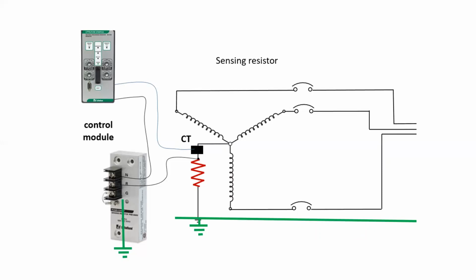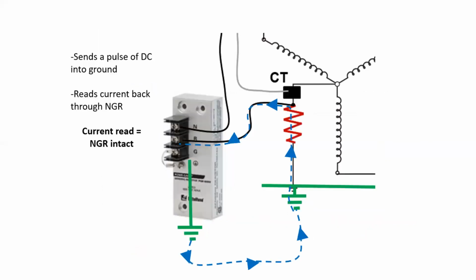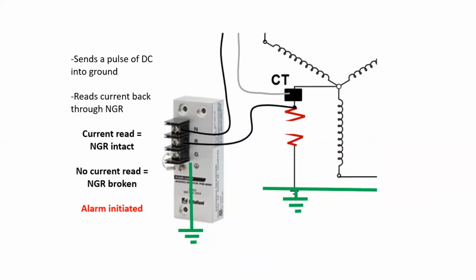And in order to accomplish that, what we typically have is something called a sensing resistor. So the sensing resistor connects with a ground terminal as well as a wire that connects to the top of the resistor. And it connects back to the control module. Its purpose is to continually verify that the resistor is intact. Now, the way it does this is actually quite clever. It sends a very small pulse of DC into the ground, and then it reads the current back through the NGR. If it senses there's current, it means that the NGR is intact. If there's no current, it means the NGR is broken, and it would immediately initiate an alarm.